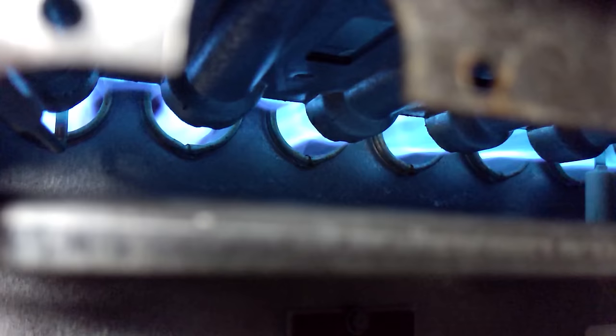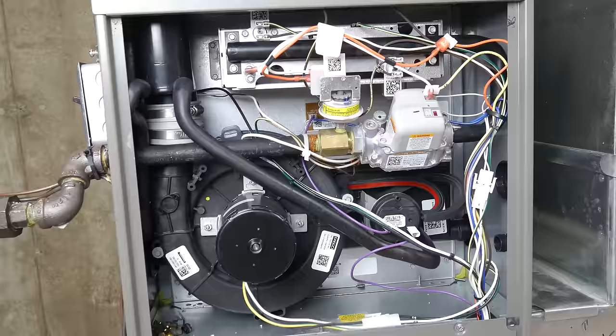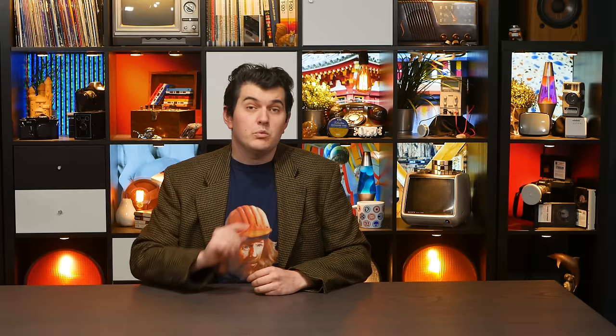Let's start by asking what the basic job of the furnace is. You might say, well obviously it's to provide heat for a living space. And you'd be more or less right. But more specifically, its job is to safely release as much of the heat energy contained in a combustible fuel as it can into the living space and distribute it with the aid of a blower fan and duct work. Nearly everything in the furnace is designed around safety, and its sequence of operations is performed specifically to prove the integrity and functionality of each of its components before it allows itself to run.